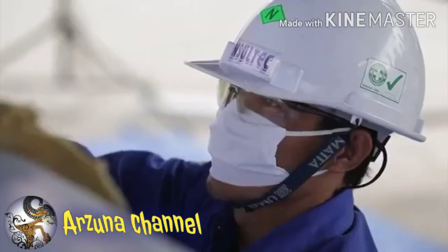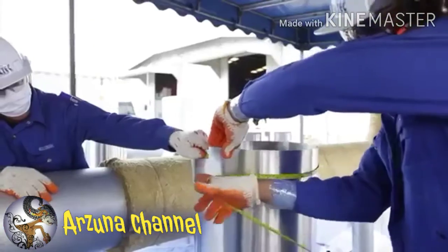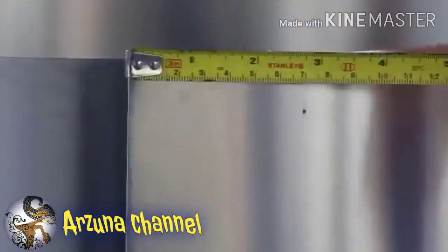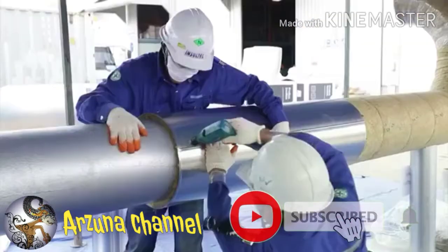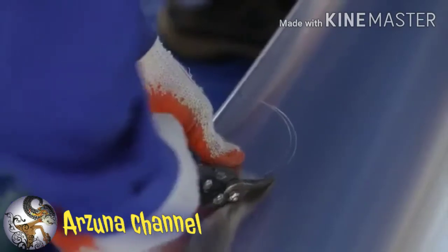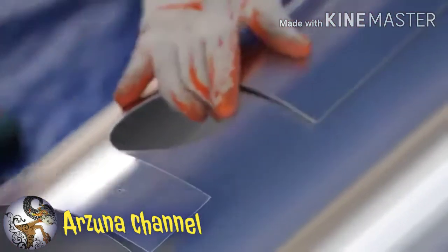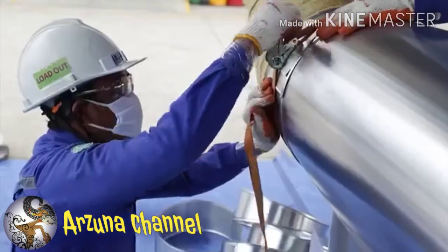Suitable cladding should be applied to protect the insulation from weather influences, mechanical loads, and potentially corrosive pollution. For doing this, the cladding has to be installed from the bottom to top along the pipe. Then, the top cladding will overlap the bottom cladding by 70 mm or as per industry standard of installation. At the pipe support section, fabricate the cladding according to the pipe support size.